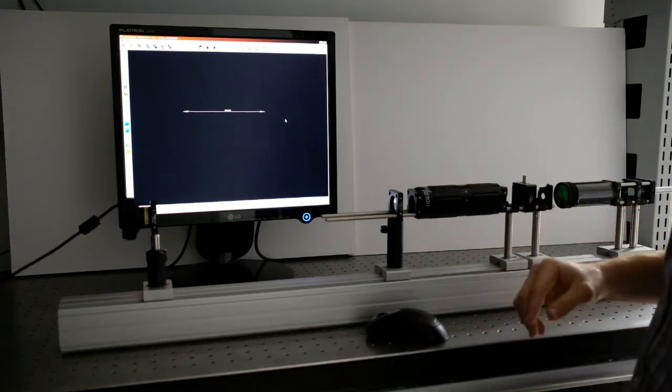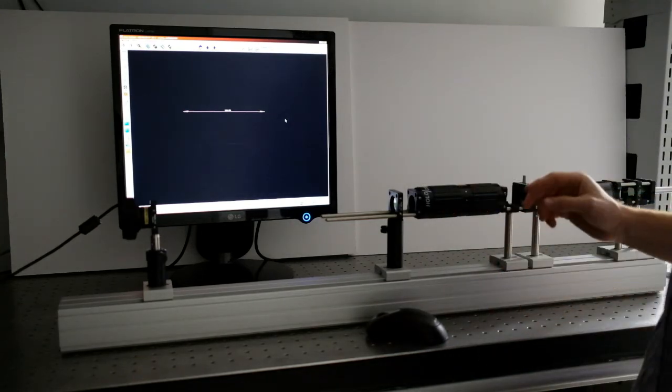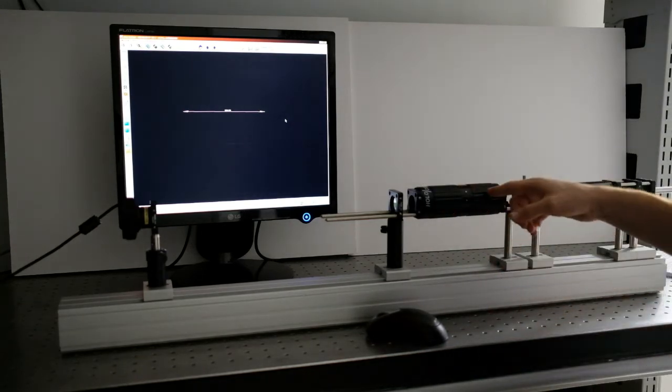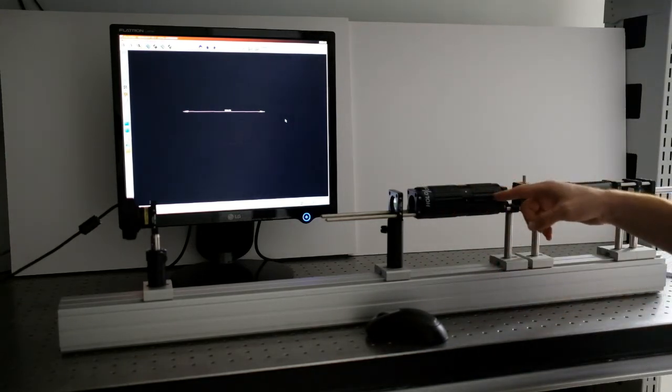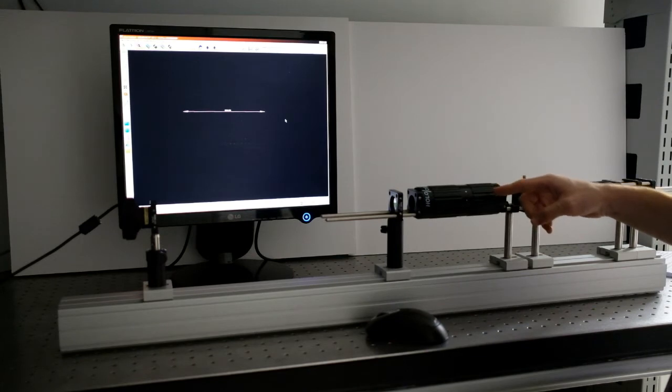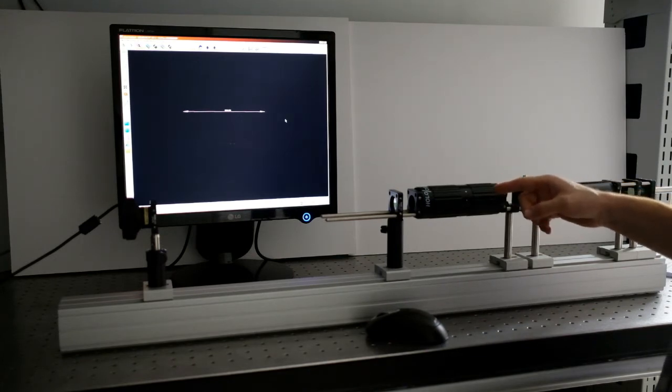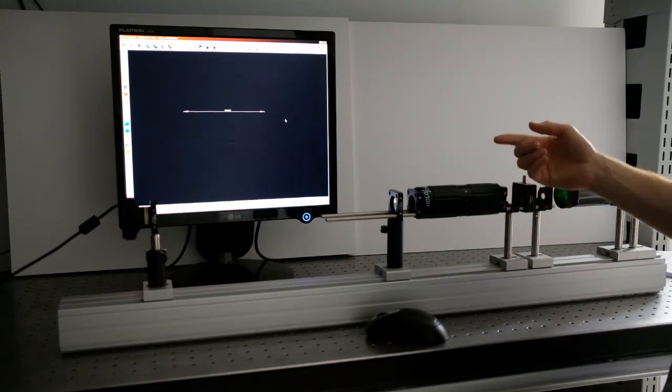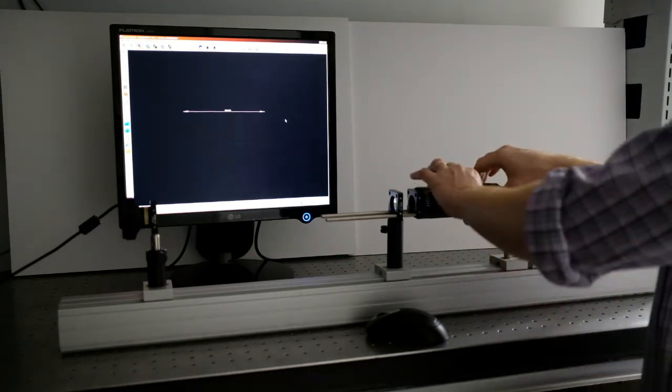As you can see, the image is now out of focus. In order to focus it, we then rotate the right-hand ring also away from the user.